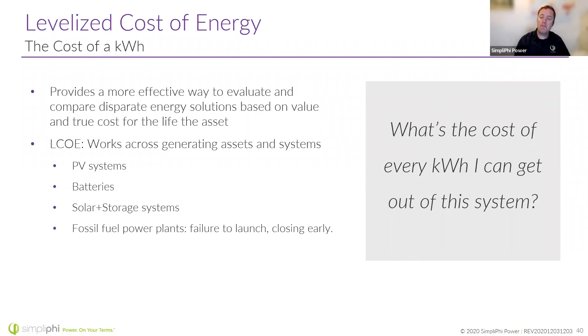Essentially you take the price of the battery over the capacity, divided by the cycles it's warranted for, times the efficiency over the depth of discharge you plan to run the battery at, and that will give you the cost of every kilowatt hour you can put in and get out of the system.